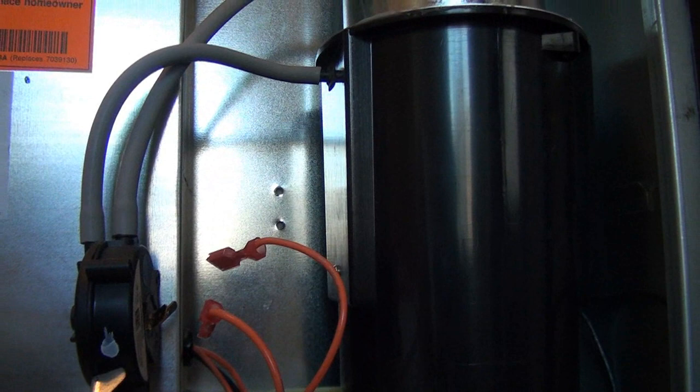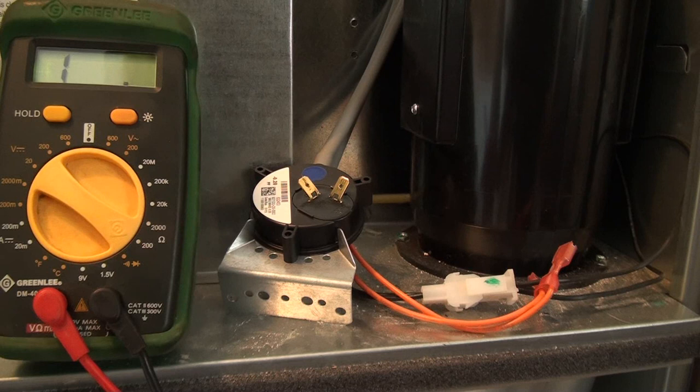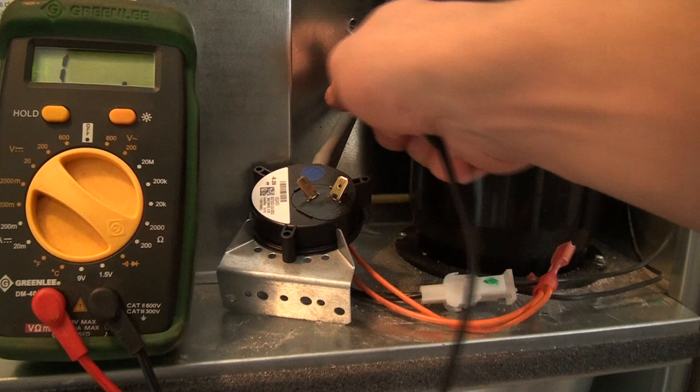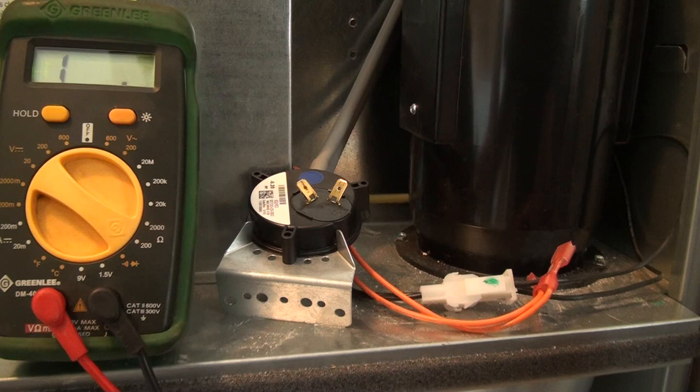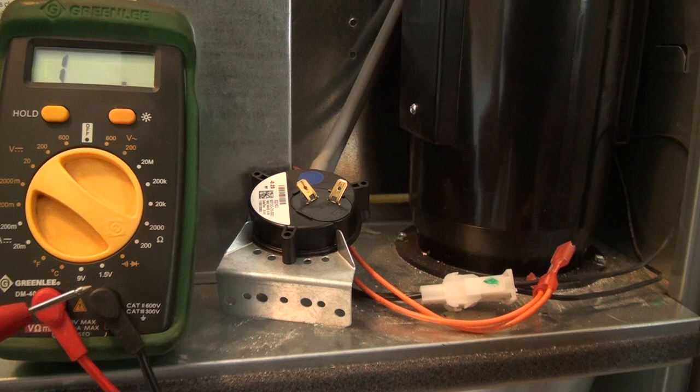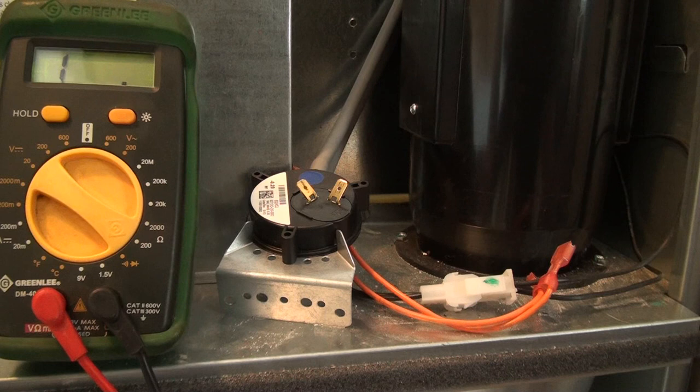Alright, so the first thing we did was we wanted to test the resistance across the switch. Because this draft inducer, basically the blower, is supposed to create a negative pressure and these vacuum tubes essentially, once there's a negative pressure, the switch should actually make contact. This is a safety mechanism so if your furnace is running or before it even starts it needs to make sure that it's got a proper draft and if it doesn't then the furnace won't fire.